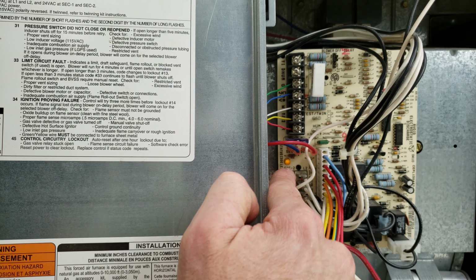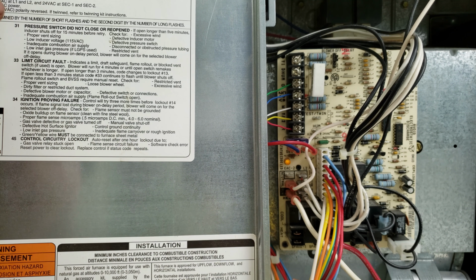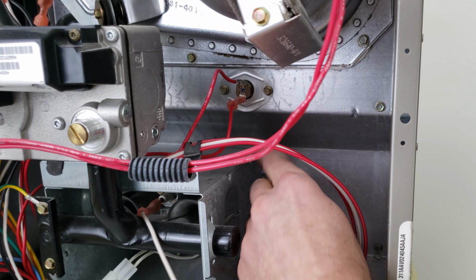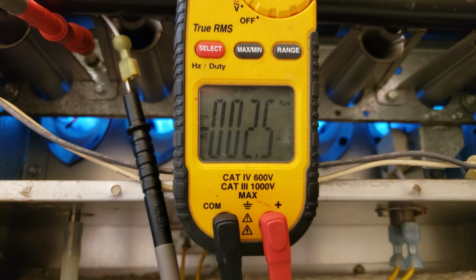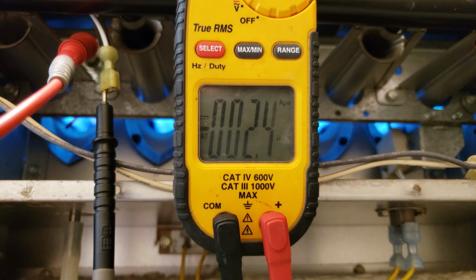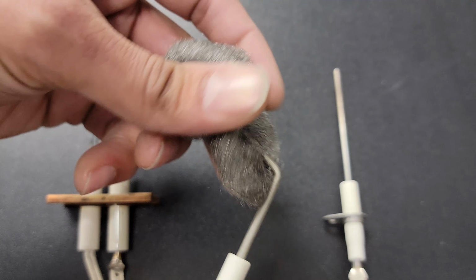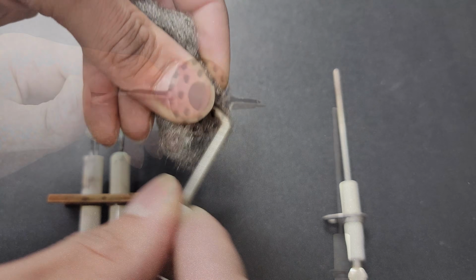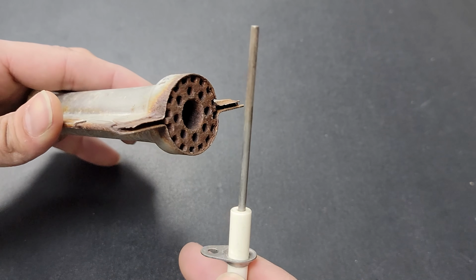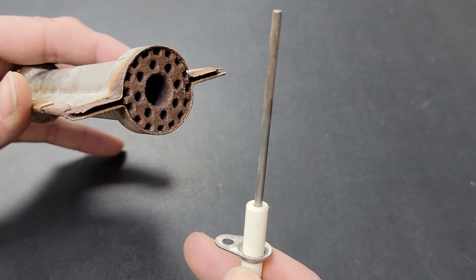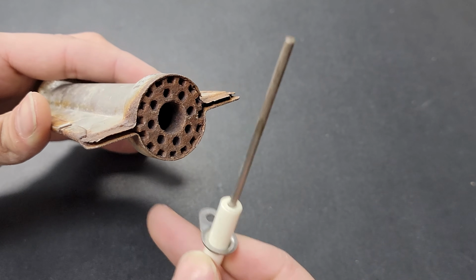So at least this gives you a place to start, and it kind of gives you the direction: hey, I need to get my manometer out and check my water column of pressure, or hey, I need to check my limit circuits and see if I have voltage drop across each of the thermal limit switches, or I need to check for flame rectification, or I have to turn the power off to the furnace and clean that flame rod. That could be a thing, or it could even be at the burner retention head itself. Maybe it's just completely rusted and it's not providing a good metal surface for the flame rectification process to occur and for the board to verify that there is a flame.